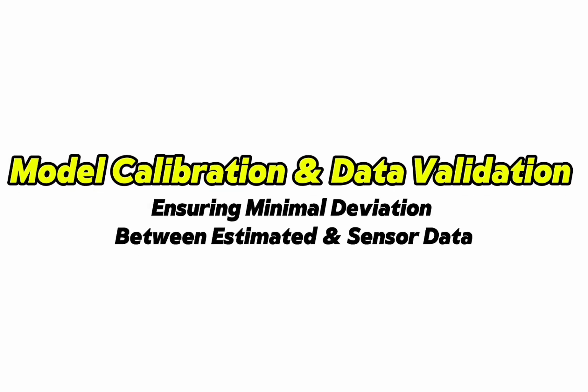Now we move into data validation. Once the data from both instrumented and non-instrumented zones is integrated, we move to validation. First, we validate pressure values using CPHEEO Urban Water Supply Standards. These standards define acceptable pressure ranges for elevated, tail-end, and normal zones. Based on this, we classify conditions as normal, low, high, or uneven.